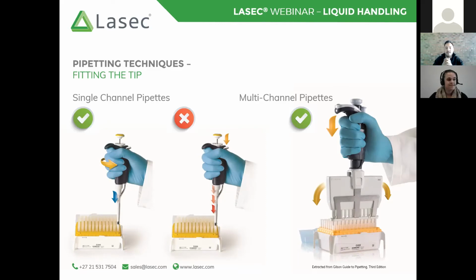Unfortunately, with multi-channels, and depending on what pipette you are using and what tip you are using, you might find that some tip boxes, although generally manufactured and structured so that it's in a 96-well format, might not line up exactly with your channels. So it is important to find a tip box or tips that do line up with those channels, whereby you can fit all those tips successfully.